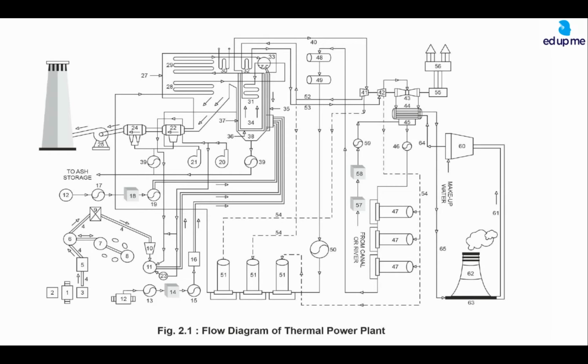No doubt, when you are starting a boiler, starting is not possible by coal. So one has to use light oil, that is a diesel kind of oil. First the light oil is fed, right? And it is ignited by something like a spark plug, which we use in our scooters or autos, right? So by spark plug, the diesel is ignited, and therefore the fire starts. Now in that fire, once again, we send the fuel oil, FO, that is heavy oil, because its calorific value is more. So once the temperature is enough, then you can start feeding coal, because then coal will start burning.